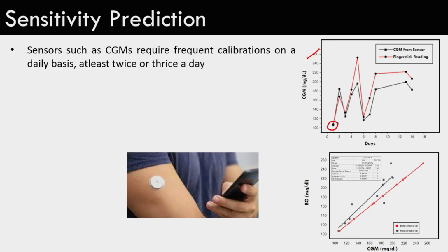Initially, it's only a one off experiment, but it gives you a qualitative idea. You see that the blood glucose finger stick reading and the CGM reading are more or less matching, but as you move on, there is a gap between the capillary blood that you are drawing from the finger prick and the measurement that is done in the CGM sensor. This is with increasing number of days.